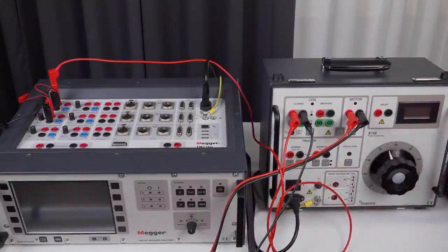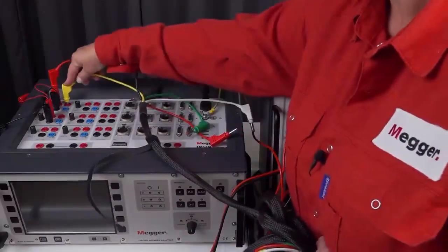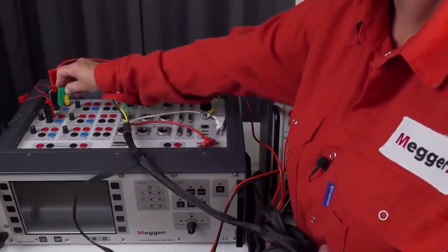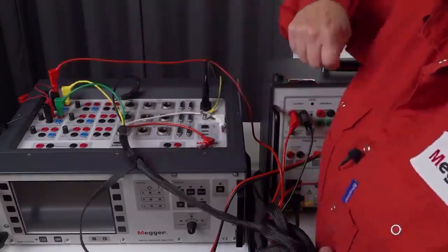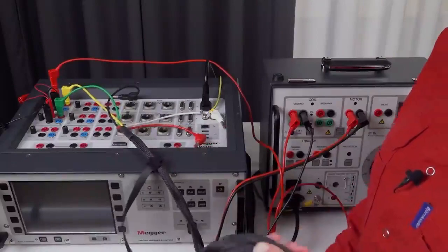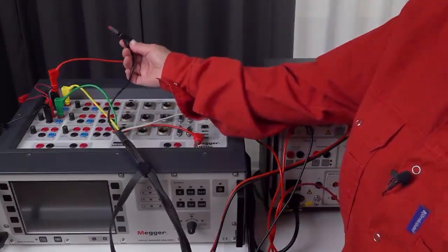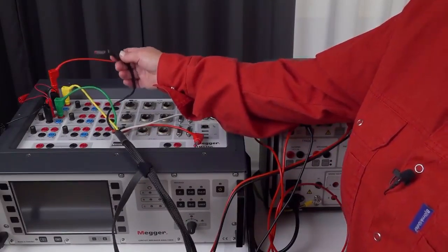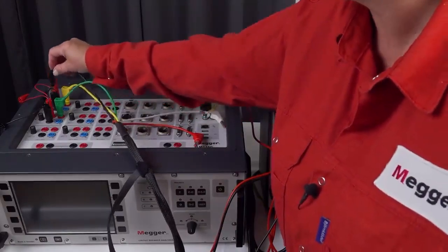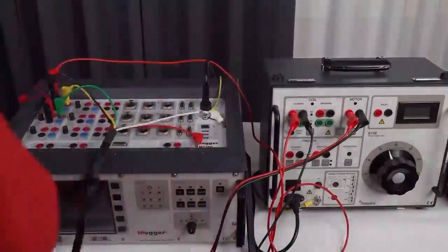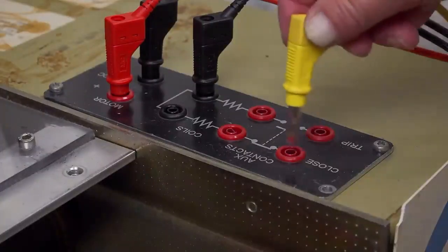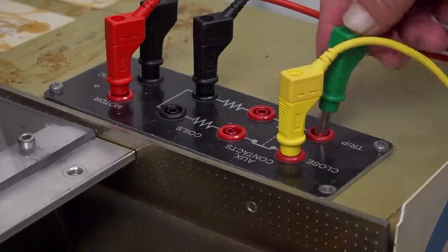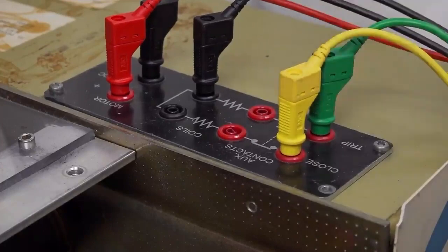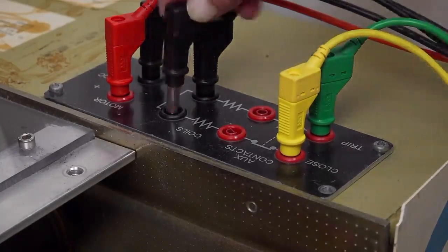I'm going to continue connecting the connections for the control of a circuit breaker. I have the close and the open on the instrument. And I also need to connect the minus, because I want the minus on the circuit breaker to meet the poles. I connect close on the circuit breaker and open on the circuit breaker. And I also connect the minus.